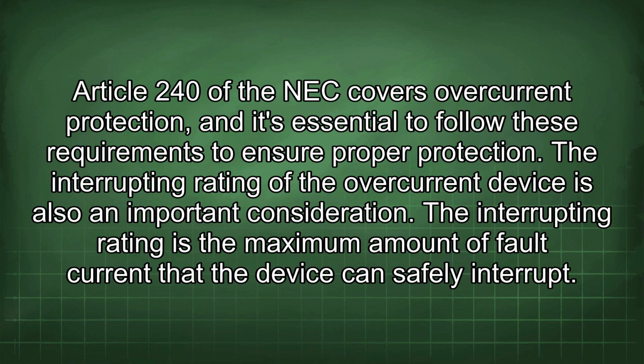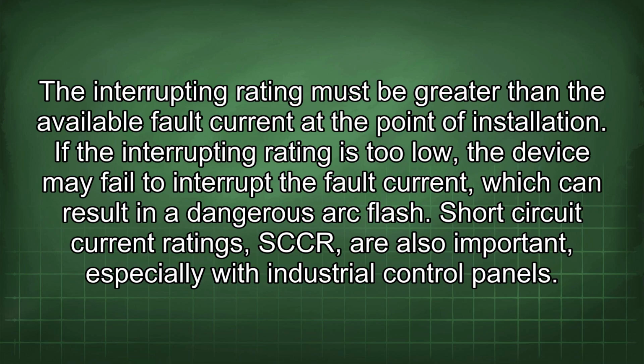The interrupting rating is the maximum amount of fault current that the device can safely interrupt. The interrupting rating must be greater than the available fault current at the point of installation. If the interrupting rating is too low, the device may fail to interrupt the fault current, which can result in a dangerous arc flash. Short circuit current ratings, SCCR, are also important, especially with industrial control panels.